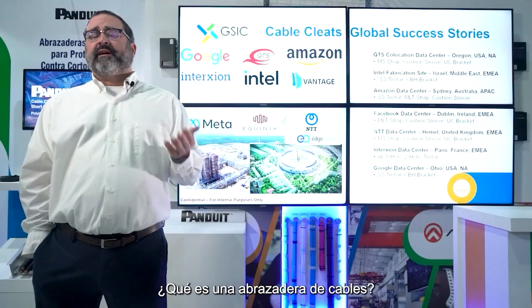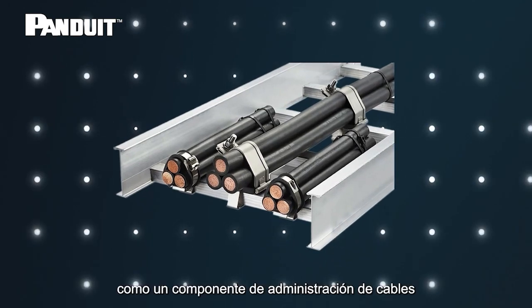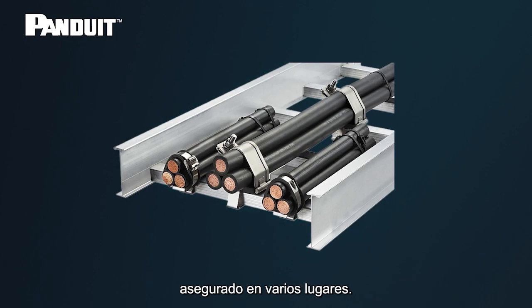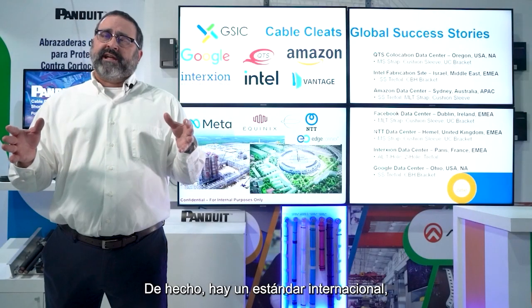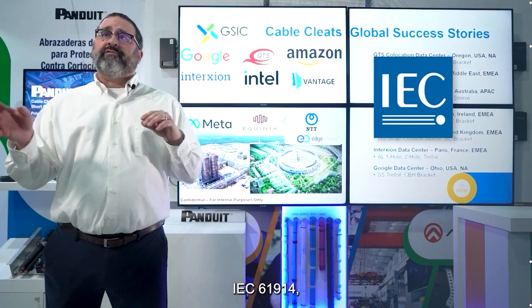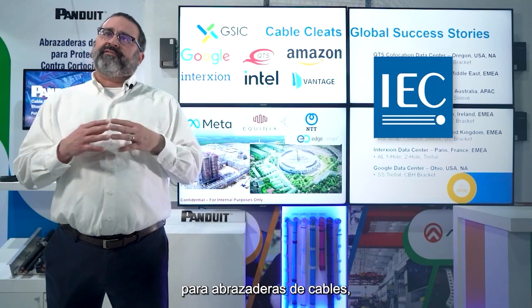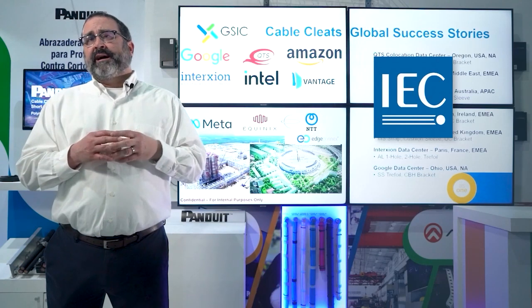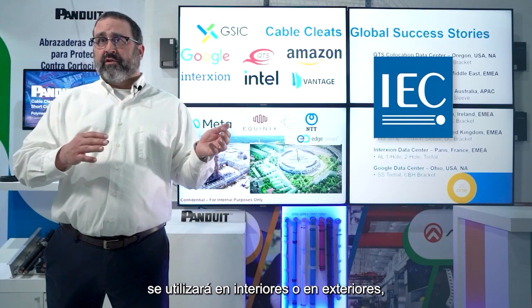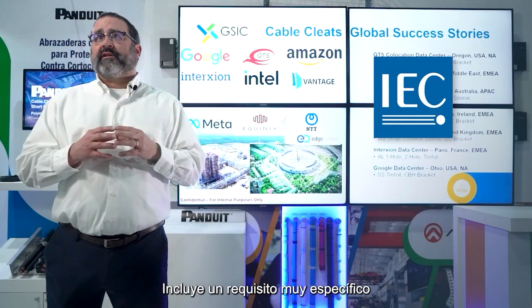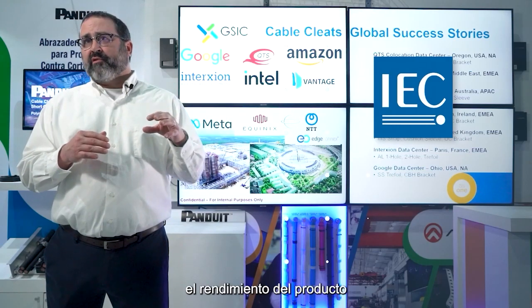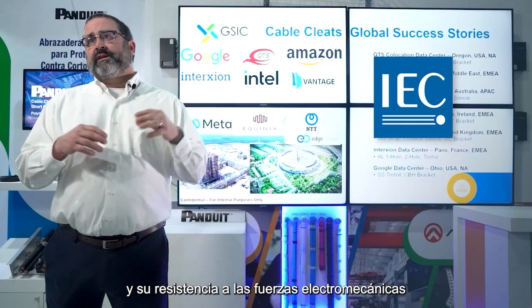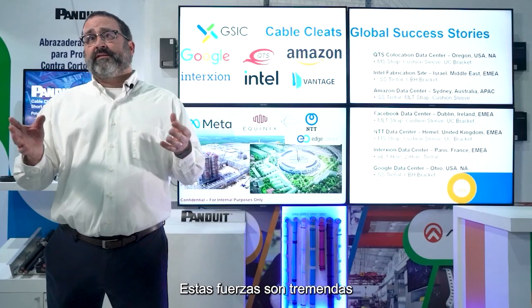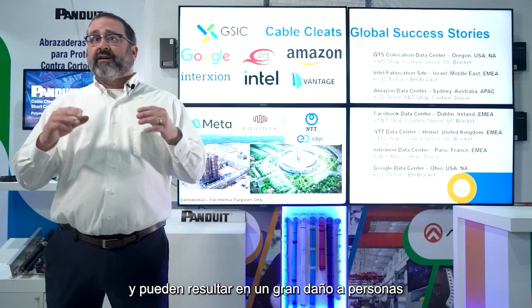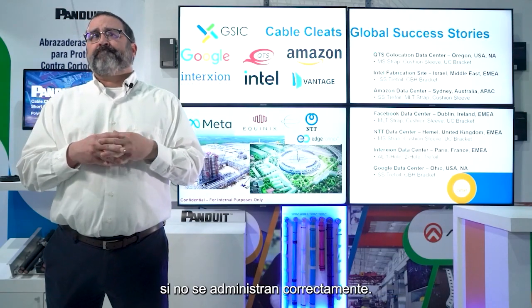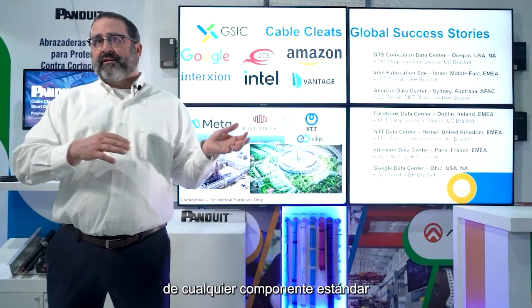So let's start. What is a cable cleat? A cable cleat is a cable management component leveraged across the length of a cable bundle, secured at various locations. There's an international standard, IEC 61914, that's regarded as a global standard for cable cleats. It defines a lot of performance characteristics for the products, establishing whether the product is used indoors or outdoors, how it should be tested, and it includes a very specific requirement at the end regarding the product's resistance to electromechanical forces that happen during a short circuit event. These forces are tremendous and can result in a lot of damage to people and property if not managed correctly. This is really what sets apart a cable cleat from any standard cable management component.